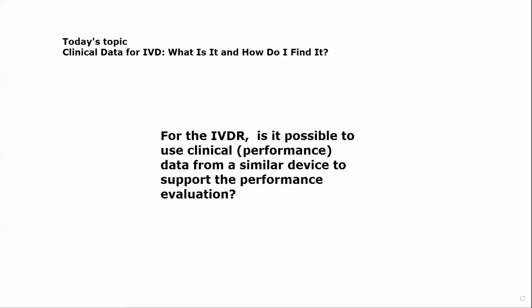Suppose you don't have any data on your device, but you have been able to successfully establish equivalence. In that case, you could use clinical data from the equivalent device to present within your CPR. But you must also make sure that you've truly established equivalence for those. If it's just a similar technology, but you're unable to establish equivalence, that's going to be a gap, and that's going to get picked up on pretty quickly.